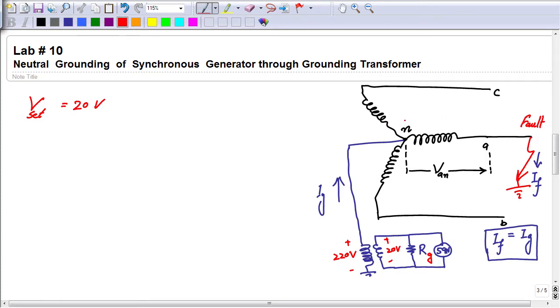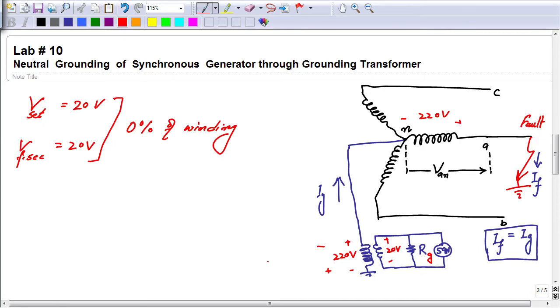If the generator winding is rated at 220 volt as well, in case of a line to ground fault at the 100% full winding, meaning the terminal of the winding, the full 220 volt will appear across the primary of this grounding transformer. That will give us 20 volt on the secondary side. So we can say VF on the secondary side of this transformer will be equal to 20 volt, which is exactly equal to V set, which is the pickup of the voltage relay. How much time would this relay take to operate? We know that when the fault voltage is equal to the pickup value, the relay is not going to trip, or it will take infinite time to trip. So it means according to this setting 0% of the winding is protected, because the fault has occurred and the relay setting is so high that it is not detecting that fault at all.